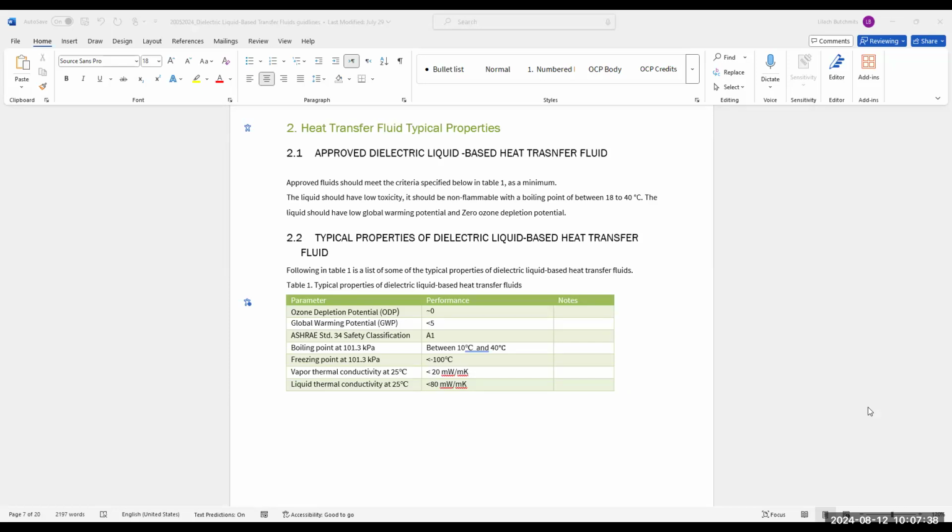The other parts are nice to have, usually a very, very low freezing point, meaning you can ship the liquid inside the system and you do not need to dry out the system before shipping, even if it's air carried. Another topic is how dielectric the liquid is. It's also a figure, and I didn't put it here, but we can. It's important to know that the liquid has to be highly dielectric, more dielectric than air. That's what you expect from this kind of liquid. So if this liquid is poured on the board, it will not do any damage to the chips or anything else.